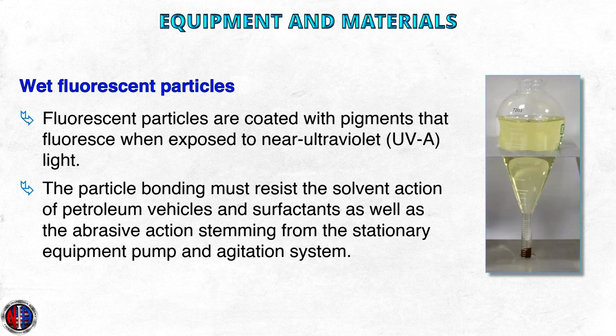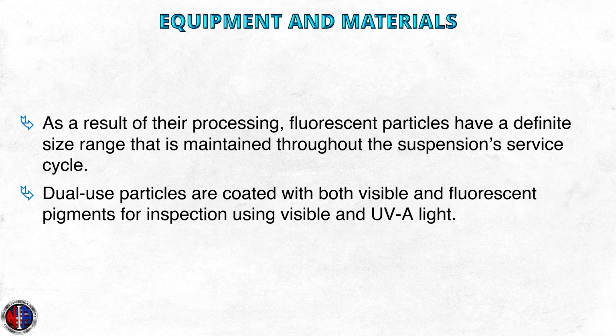Wet fluorescent particles. Fluorescent magnetic particles involve bonding pigments around each magnetic particle. This bonding must resist the solvent action of petroleum vehicles and surfactants, as well as the abrasive action stemming from the stationary equipment pump and agitation system. Some manufacturers also encapsulate the bonded dye particles in a layer of resin. As a result of their processing, fluorescent particles have a definite size range that is maintained throughout the suspension service cycle. Dual-use particles are coated with both visible and fluorescent pigments for inspection using visible and UVA light.